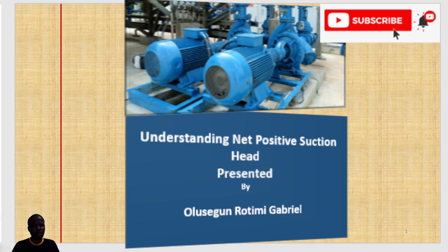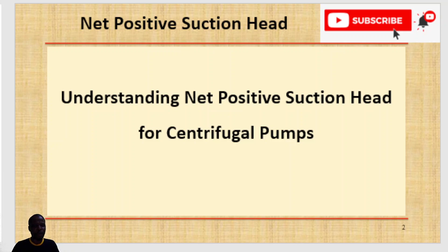Welcome to our YouTube channel. Today we'll be looking at understanding net positive suction head (NPSH) for centrifugal pumps. A very important consideration in selecting a centrifugal pump is the conditions existing on the pump suction system, and these conditions are best expressed as the NPSH. Since centrifugal pumps are incapable of handling large quantities of vapor, the pump's external suction system must be provided with sufficient absolute pressure to prevent vaporization or flashing in the impeller.